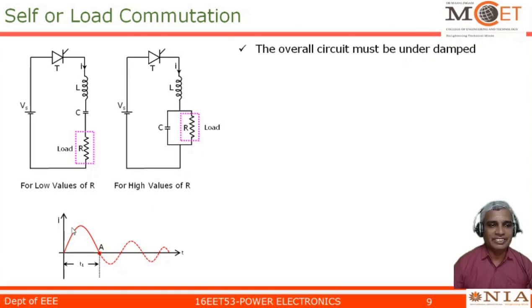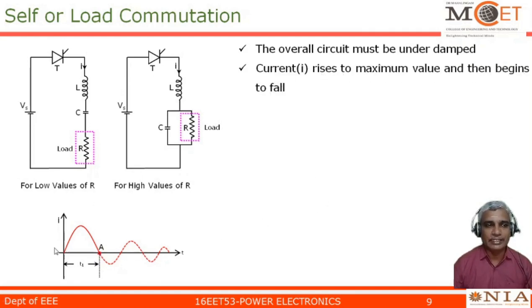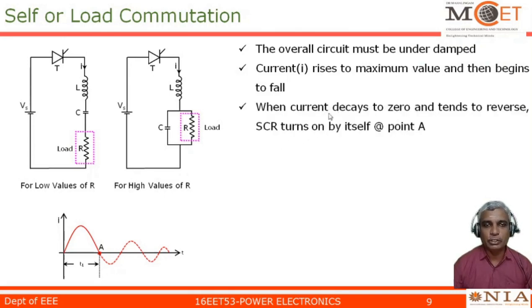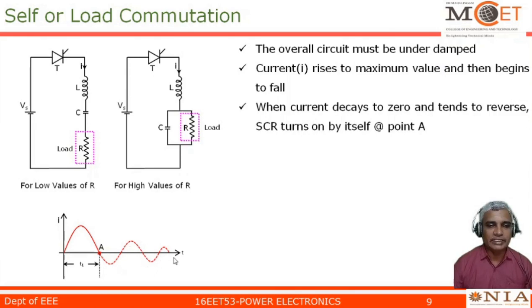The overall circuit must be an underdamped circuit. In an underdamped circuit, the DC current will not die out naturally to zero directly — it will cross zero and oscillate for some time before settling to zero. Current rises to a maximum value and then begins to fall, and when the current decays to zero and tends to reverse, the SCR turns off by itself at point A. This is very similar to what we have seen in natural commutation. The overall circuit being underdamped is the important condition to make the current waveform cross zero so that the device naturally turns off.